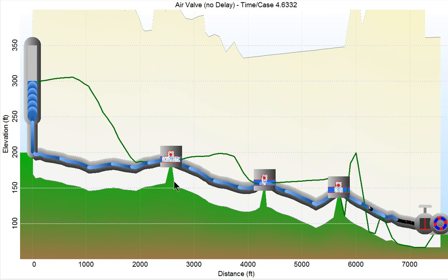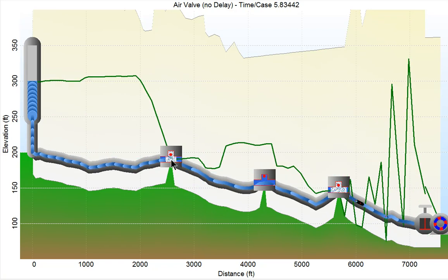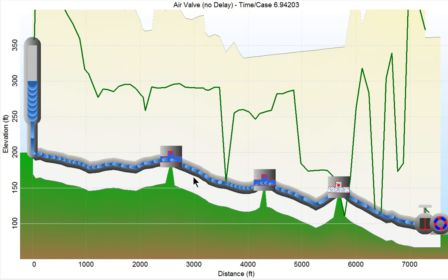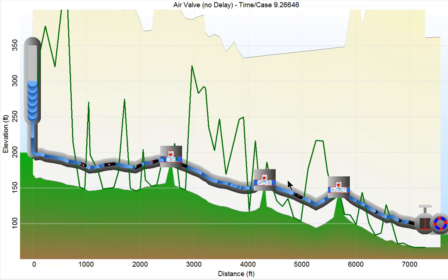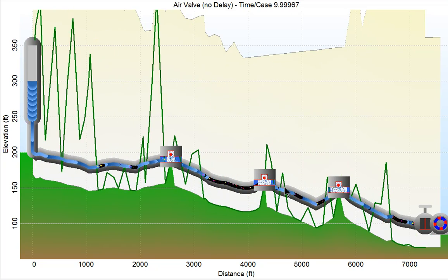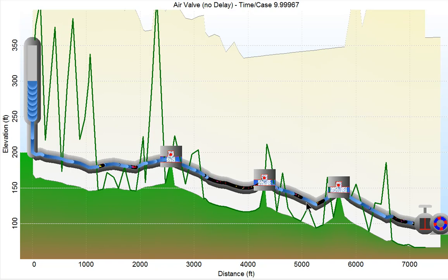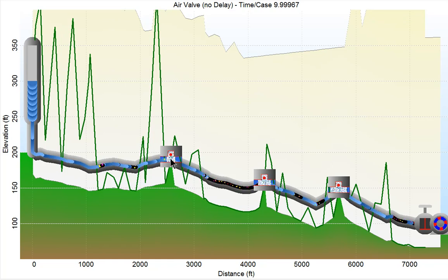The air valves are pulling in air, but as the air is expelled, you get a big pressure spike, and when that happens you start getting spiking around and cavitation forming. The final result is basically almost as bad as with no surge protection. These air valves were nominal — four inch in and four inch out — and they are known to often release air too quickly, causing air slams. There are anti-slam air valves that would do a better job at eliminating those air slams.